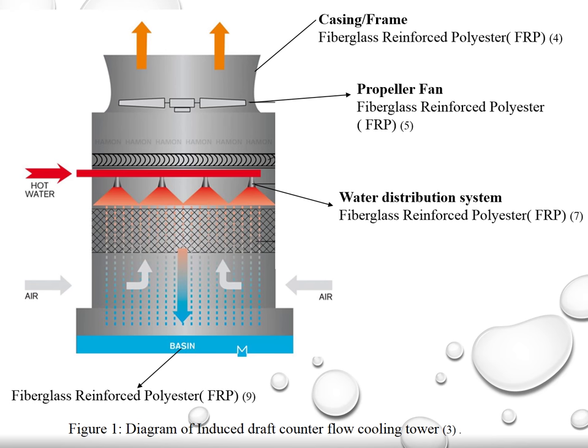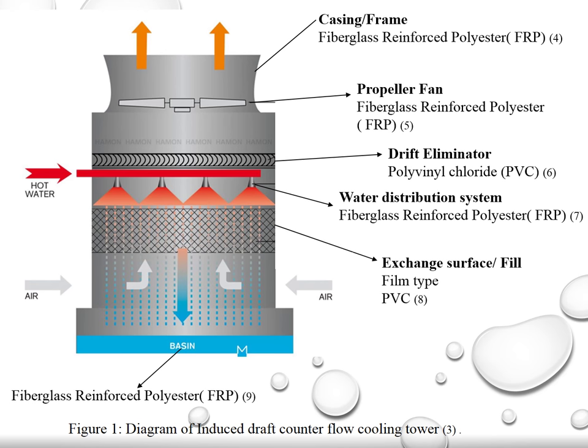Polyvinyl chloride or PVC is used for the drift eliminator, as it has high resistance towards weather, chemical, and corrosion. For the fill, film type PVC is used as it lowers the pumping head and horsepower cost for counter flow.